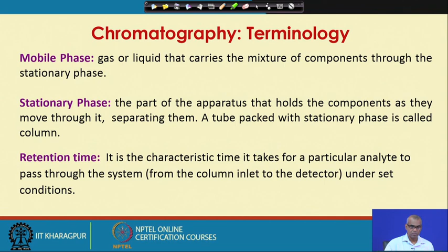Retention time is the characteristic time it takes for a particular analyte to pass through the system from the column inlet to the detector under set conditions. So, retention time is the time elapsed between the injection and the detection. Retention time depends on the component in the mixture. So, looking at the retention time, I should be able to identify the component. Chromatograph is the instrument employed for chromatography, and chromatogram is the detector versus time signal.